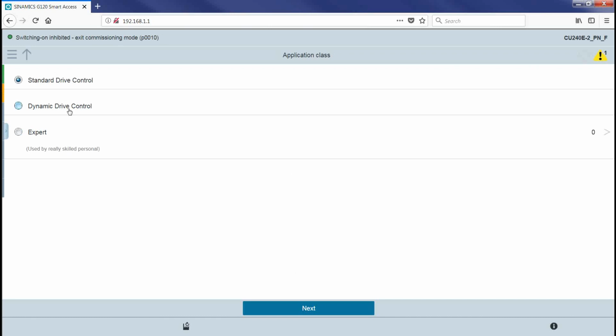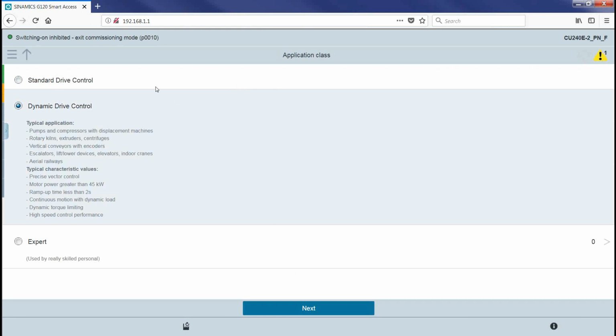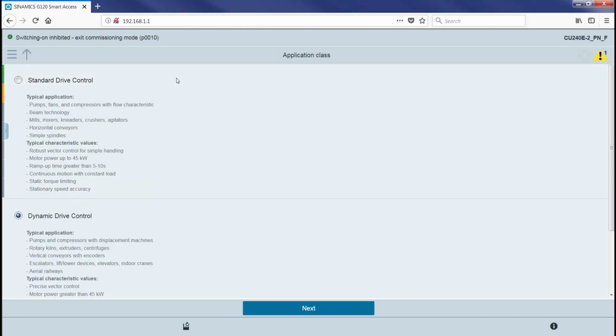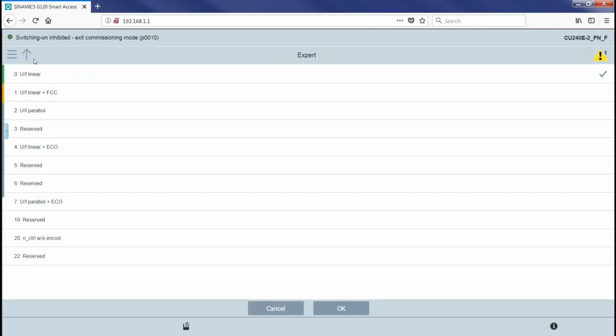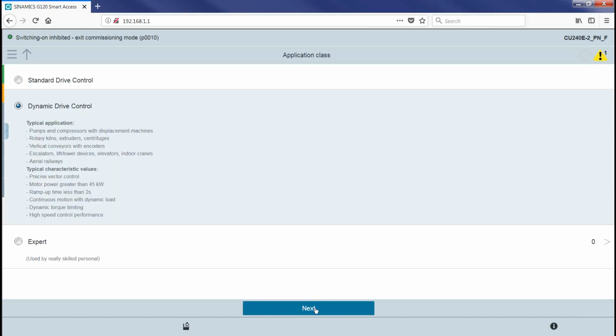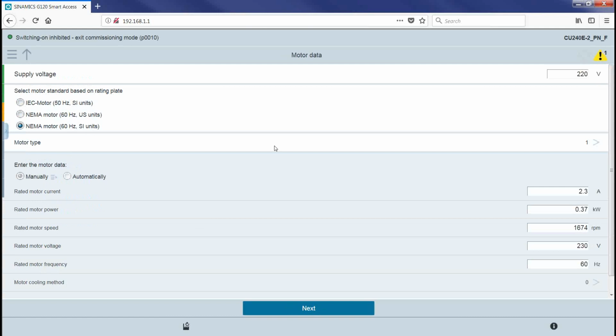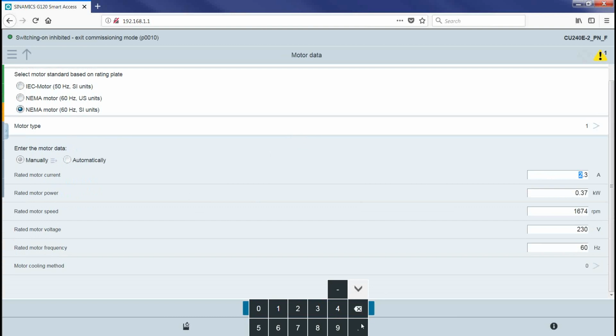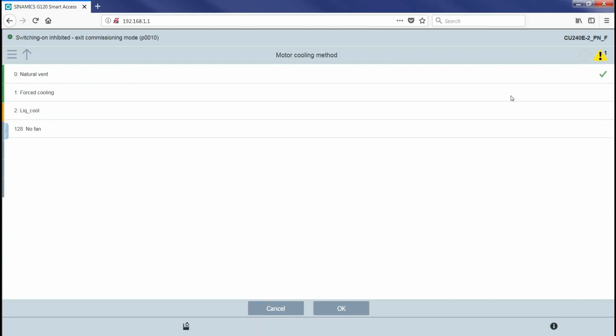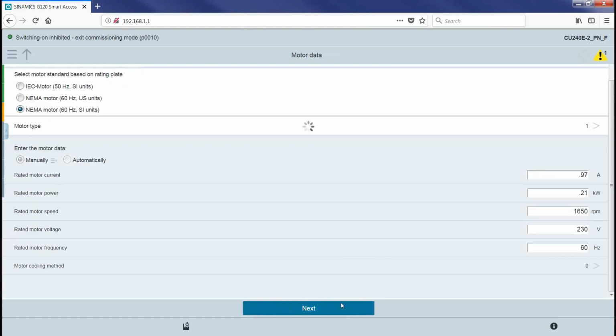So for this example, I'm going to click dynamic drive control. Again, if you highlight out here and click, it'll show you kind of what that would be used for. Typical applications, typical characteristics and values. There's standard, there's dynamic. Expert's got some selections to make. Oh, cancel expert, so I'm going to do dynamic. Next. Again, NEMA motor, well, I'm going to use SI units just because of what my motor is. Manual. Again, 0.97 amps, 0.21 kilowatts, 1650 RPM, 230 volts, 60 hertz. Motor cooling method is going to be just natural ventilation, so just a standard induction motor. Then go to next.